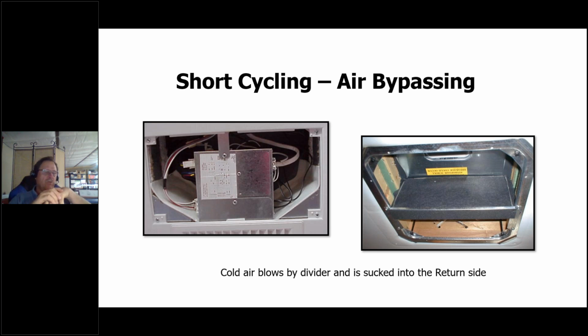Imagine what that does to your delta. It's bad enough that you're getting warm air out of the compartment where the human is, but add some attic air with it. So if you only have, say, a 14 to 22 degree delta, and the input heat cranks up because you've got hot air coming out of the attic, what did you just do to your ability to cool the coach? Yeah, you decreased its ability.